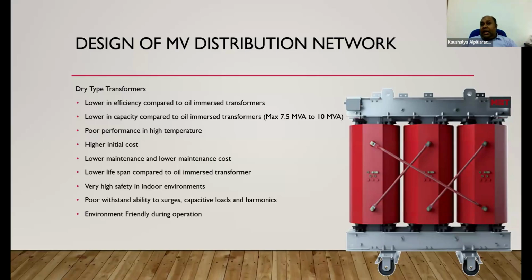equip with extra cooling fans. So oversizing depends on your K rating, or you can have a K rated transformer. That's a bloody meaty transformer, which can withstand and live with harmonics. That doesn't provide the efficiency. That's not efficient at all. What we have to do is we have to filter those harmonics using maybe active filters or passive filters or any other mechanism, and make the system efficient.